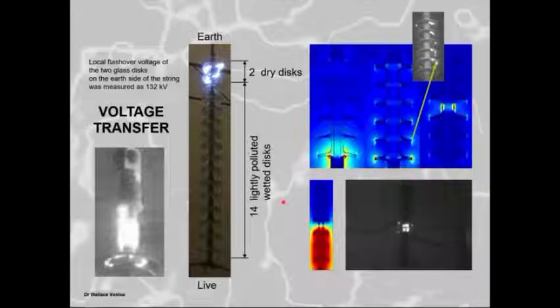And this is something you need to be careful with when you're replacing shattered glass discs. Here I put up in the lab a 16 glass disc string with 2 dry glass discs, and the rest was wetted and polluted. And you can see that the string basically flashed over the 2 discs on the earth side. So when you replace a broken disc on a string, rather replace the whole string than just the disc, or clean the whole string so that they are all equally the same.